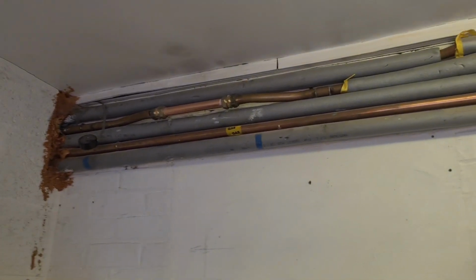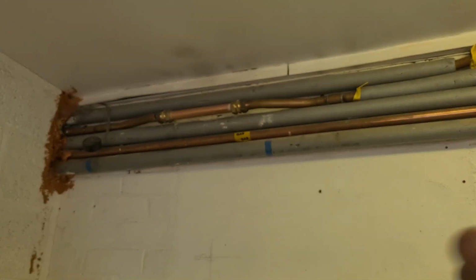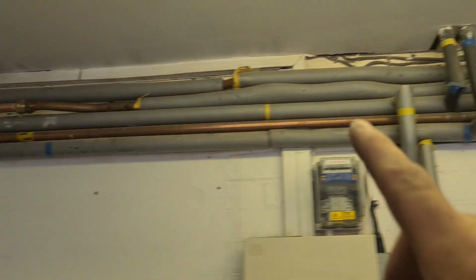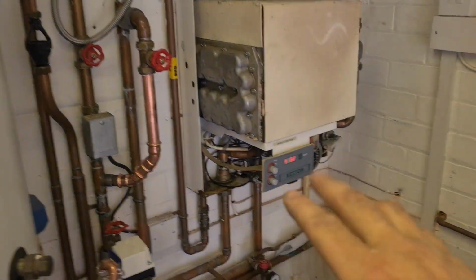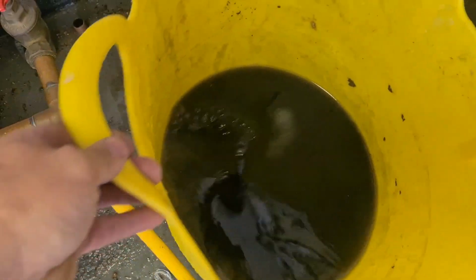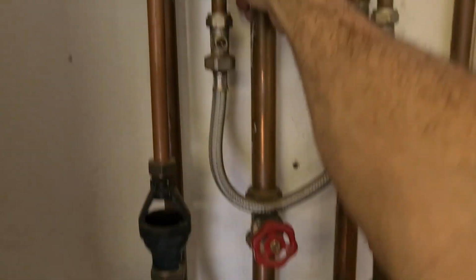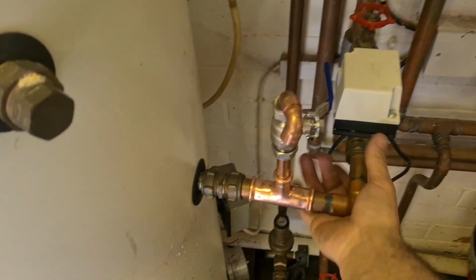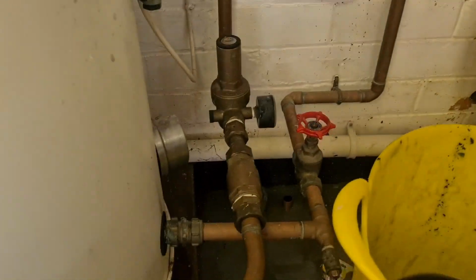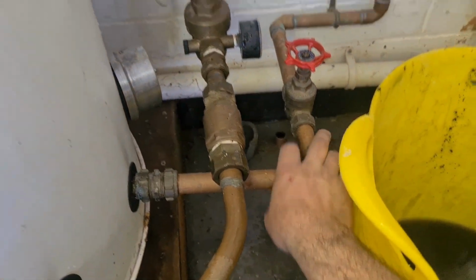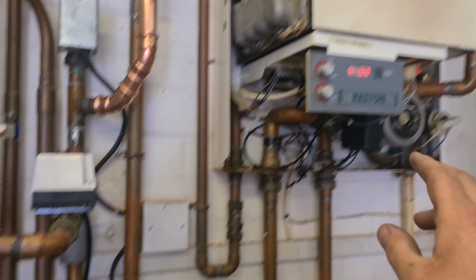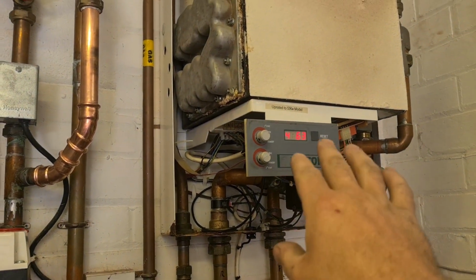Right, so following on from that pump being taken out, my flow through there is now going through at maximum temperature. If I follow it back down here now, there are still a few underlying issues with this system. You can see straight away by the colour of the water, sedimenting up to hell. But again, my flow straight off my heating valve there is red hot. Flow to my cylinder's red hot now. I'm getting flow down my return, so that's getting nice and warm. Boiler stabilised, it's modulating down like it should be doing as well.